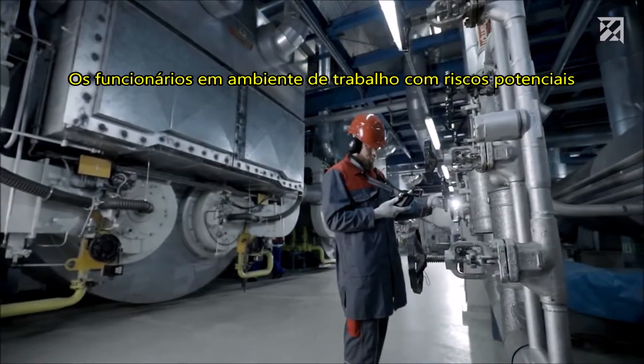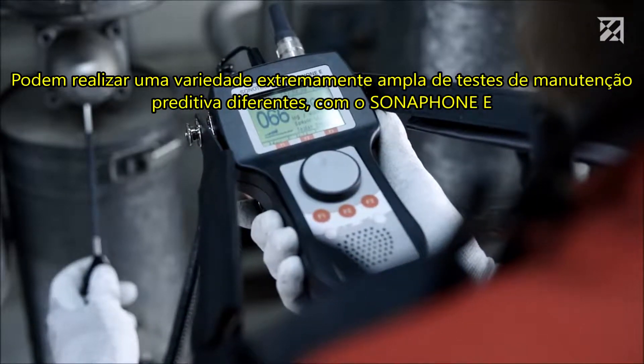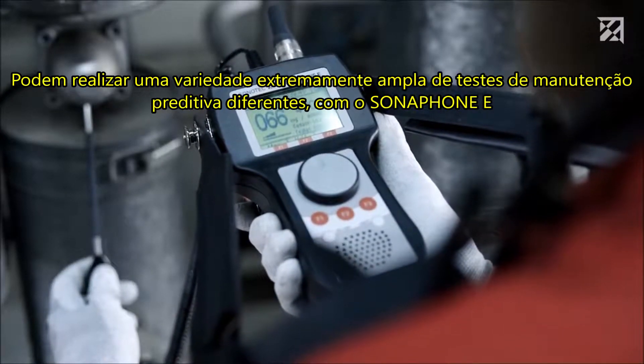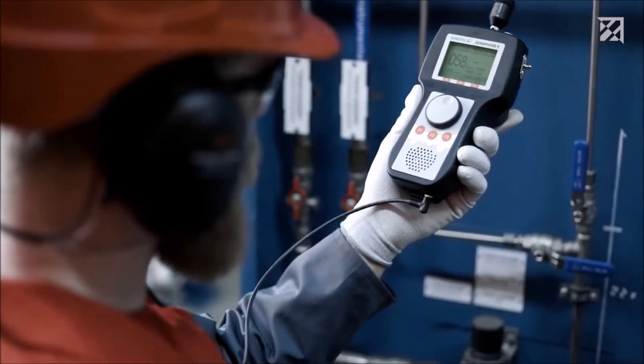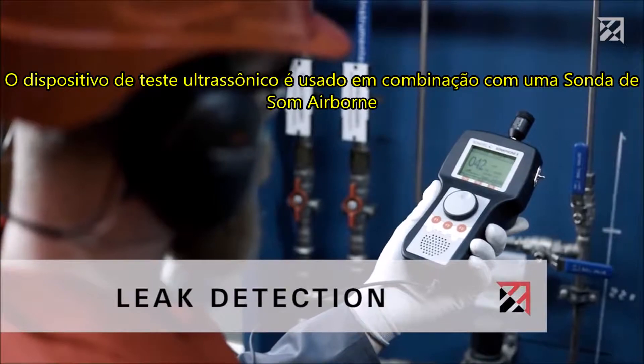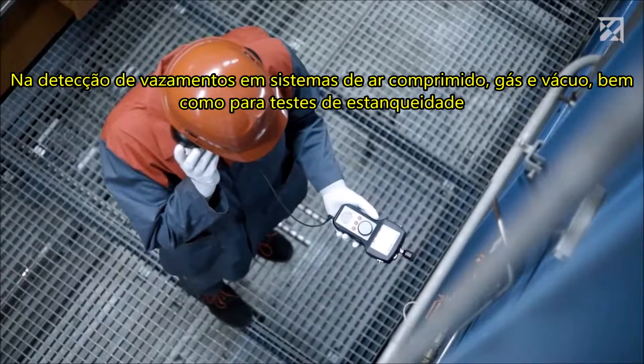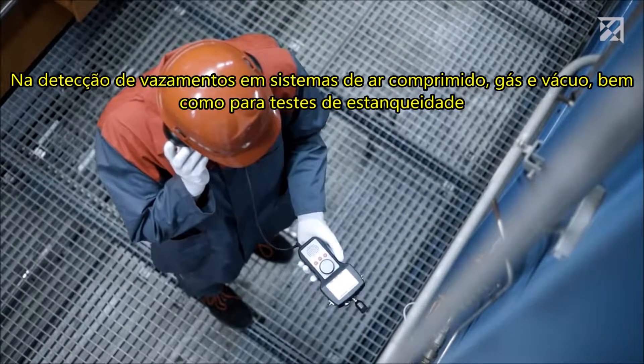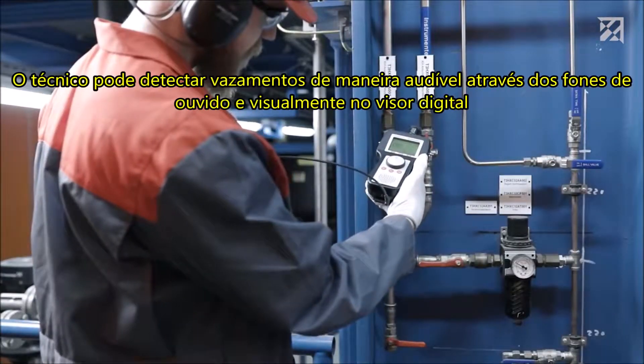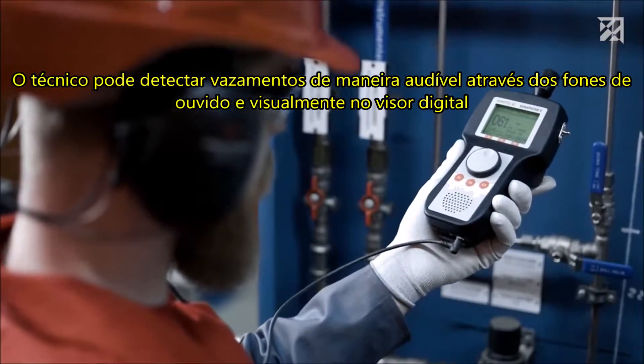Employees in potentially hazardous working environments can carry out an extremely wide range of different predictive maintenance tasks with the SonaPhone E. The ultrasonic testing device is used in combination with an airborne sound probe for the detection of leaks in compressed air, gas, and vacuum systems, as well as for leak tightness tests. The technician can detect leaks both audibly via the headphones and visually on the digital display.